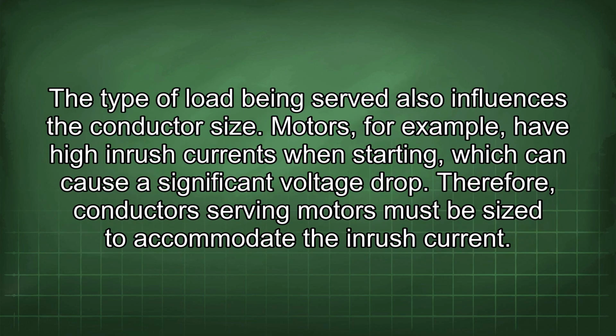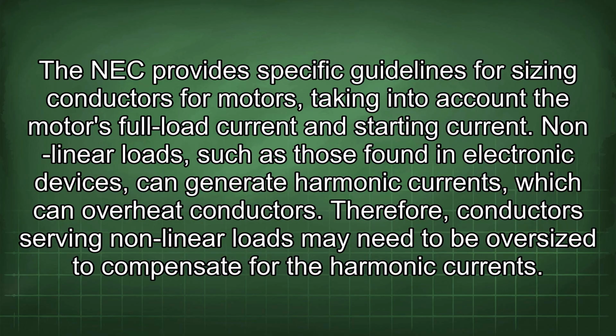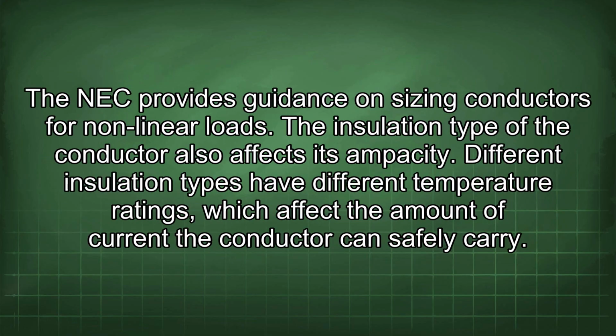The type of load being served also influences the conductor size. Motors, for example, have high inrush currents when starting, which can cause a significant voltage drop. Therefore, conductors serving motors must be sized to accommodate the inrush current. The NEC provides specific guidelines for sizing conductors for motors, taking into account the motor's full load current and starting current. Nonlinear loads, such as those found in electronic devices, can generate harmonic currents, which can overheat conductors. Therefore, conductors serving nonlinear loads may need to be oversized to compensate for the harmonic current. The NEC provides guidance on sizing conductors for nonlinear loads.